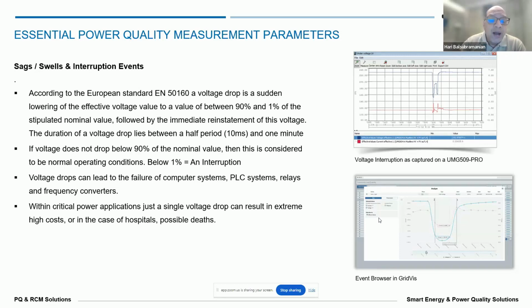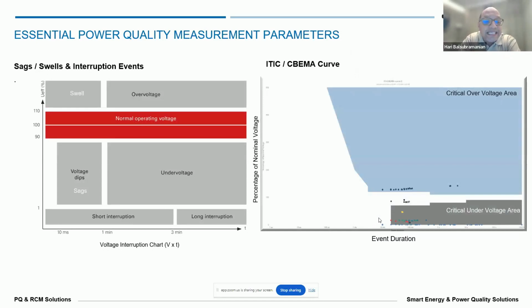And then we also have 90% of the nominal value, when the voltage reduces for a very short time, from a half cycle to 1 minute. This can also be classified as a sag. That's what the next slide says: a voltage dip from 10 milliseconds to 1 minute is classified as a voltage sag, and beyond 1 minute it can be called an under voltage. Terminologies vary from country to country and manufacturer to manufacturer, but the crux is that an under voltage happens from 10 milliseconds and can go higher and higher, up to whatever time we have. For example, sags are considered as an event which happens between 10 milliseconds, which is half a cycle, and 1 minute in a 50 hertz network.